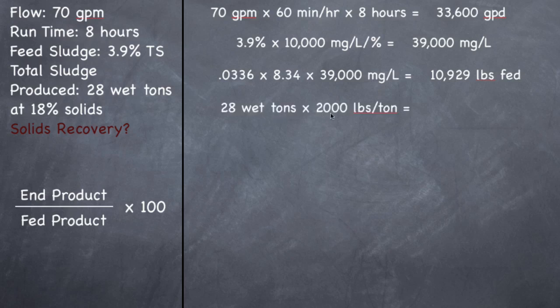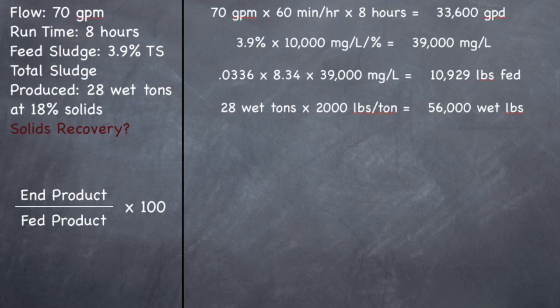So 28 wet tons times 2,000 pounds per ton gives 56,000 wet pounds. If you put this on a scale, it would weigh 56,000 pounds, and it's 18% solids. Since we need to compare on the same 100% dry basis, multiply 56,000 times 0.18. That gives 10,080 dry pounds.